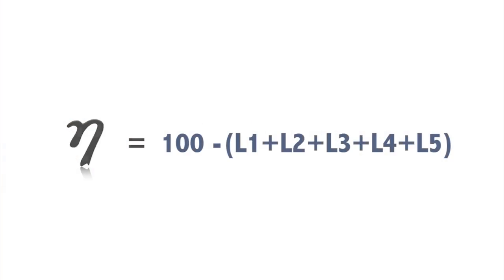Another method of determining the boiler efficiency is by actually working out all the losses that are happening in a boiler, and then 100% minus the sum of all losses would give you the efficiency of the boiler. Now both the methods give you the efficiency of the boiler. In the second method, to calculate the boiler efficiency, you need to calculate all the losses. And when you have the breakup of the losses, you know exactly which loss is contributing in a bigger way to the boiler efficiency and which loss really should not be focused upon.